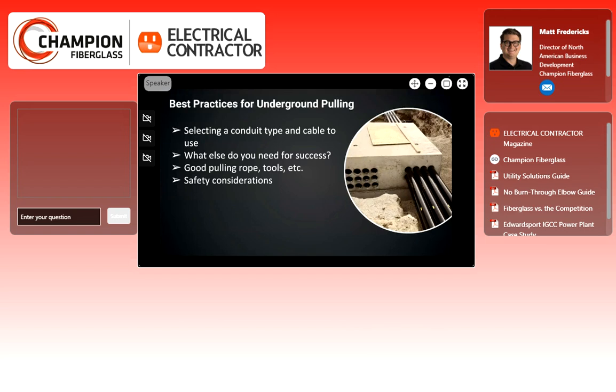Different types of tools are needed. Swivels are great for reducing overall pull tension through sweeps or straight lengths. Do you want a basket style pulling grip, a crimp-on pulling head, or a reusable power pulling eye? There are so many tools now to reduce tension on the conductor and pull successfully through an underground cable system. Take the time to meet with your local rep from any pulling equipment manufacturer or company that helps with pulling success - it's amazing the tools they have now.